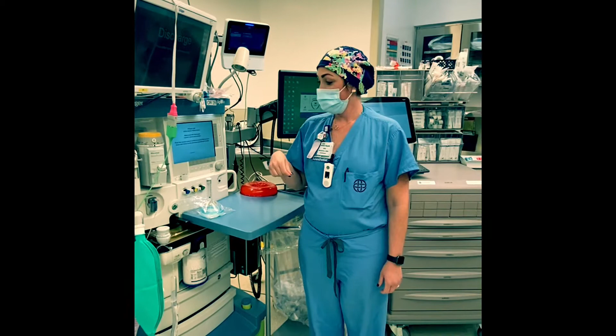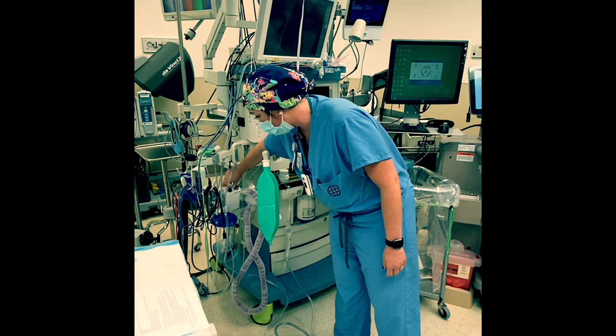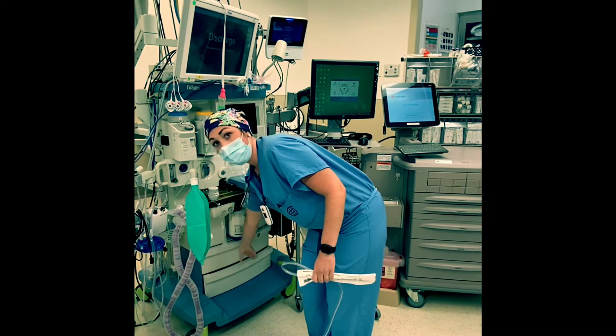So you're going to make sure that your suction is here. Your suction canister is going to be here. Turn it on and off here. If it's not on, just turn it to max. Make sure that there's a Yankauer on the end of your suction. Make sure it works. And if there's not a Yankauer, it's going to be in one of these two drawers underneath your ventilator. Then you're going to turn your machine back on, and this is the part that takes a minute.